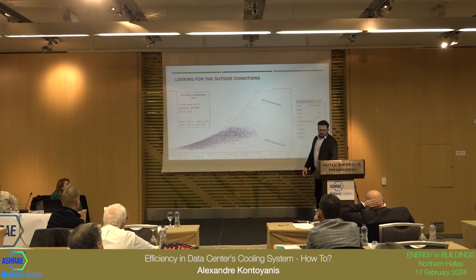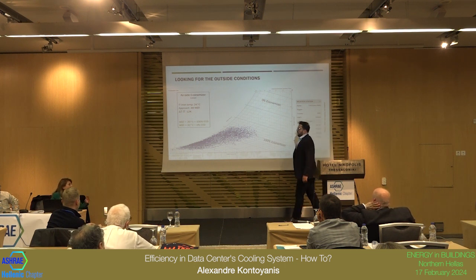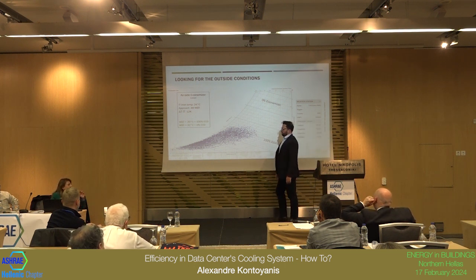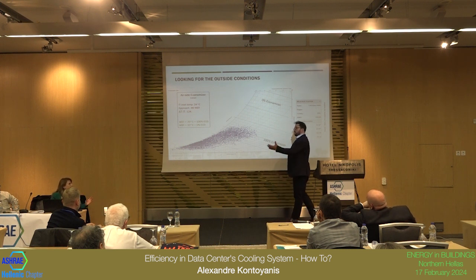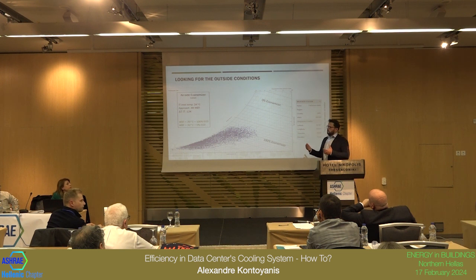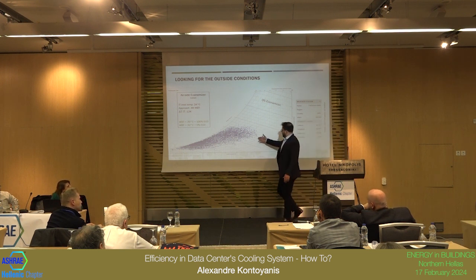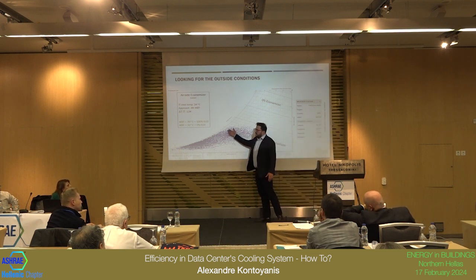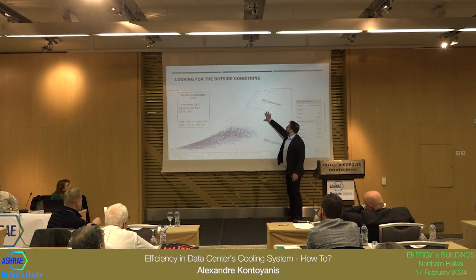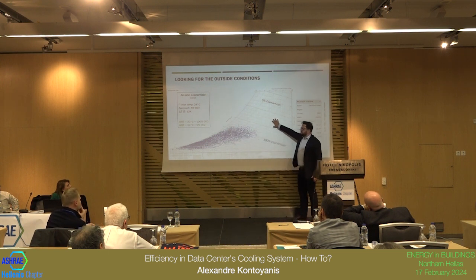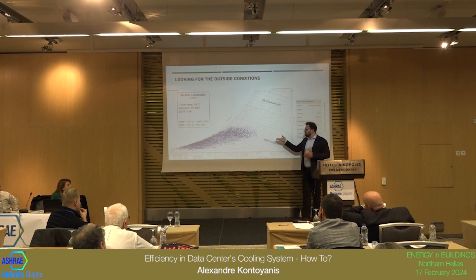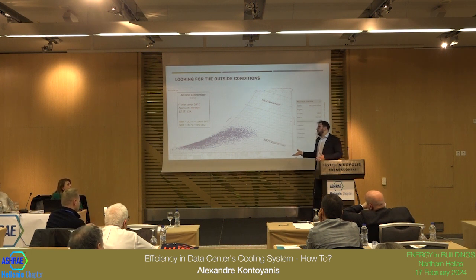It's tough to make this achievable all around, because we need to be sure that even on the hottest day, the data center will operate. But if you can drop the temperature, for example from 35 to 25, you can go around this. You can do partial cooling. Your chiller is now cooling 25 to 18. You will need the chillers. It's possible, yes, and you can use it as a backup or work with chillers.